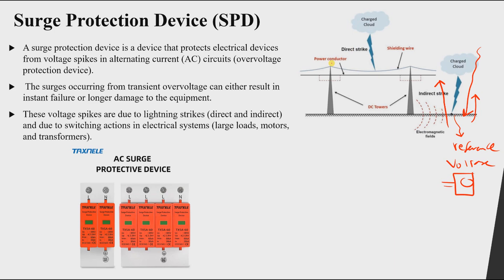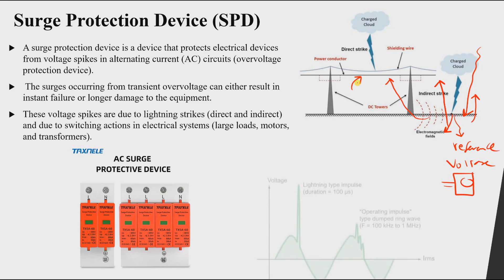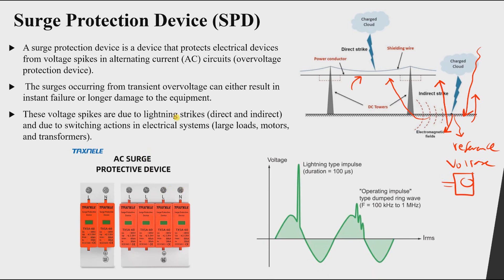When the lightning strikes the ground, remember it is a current flowing to ground — a very large current. This produces large electromagnetic fields that can affect nearby transmission lines and induce voltage on them, similar to coupling phenomena. So an indirect strike can cause overvoltage in two ways: by raising the ground potential and by inducing voltage through electromagnetic fields.